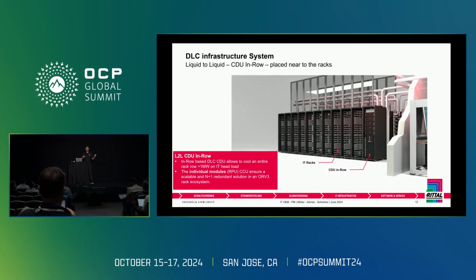So some of the applications around it, and give some examples of this modularity. This is a very typical example, 10 IT racks operating at 100 kilowatts each, possibly. And on the end, as the name suggests, an Inrow product sitting right at the end. I mean, if those racks, as an example, were operating at 50 kilowatts each, half a megawatt in there, you could scale this one down a little bit and scale it up at a later date, in a few months from now.